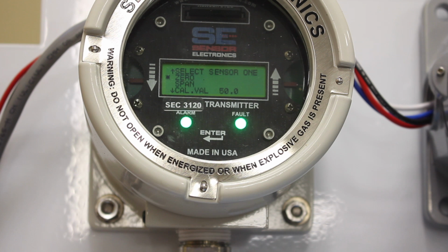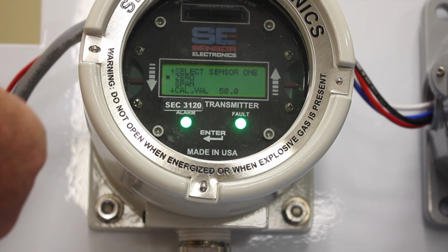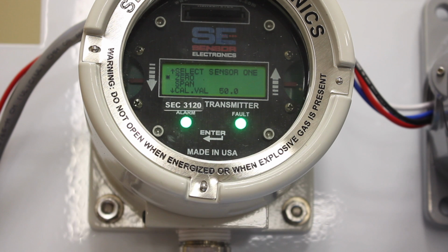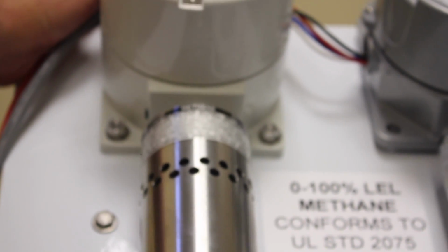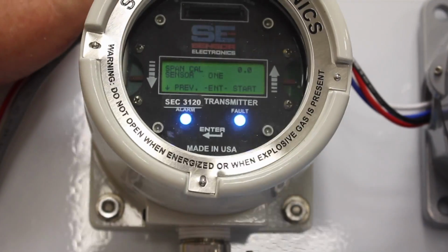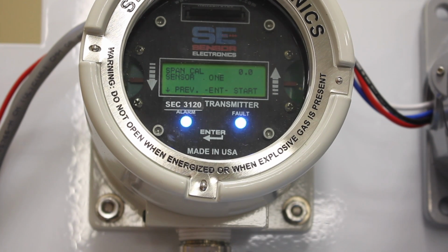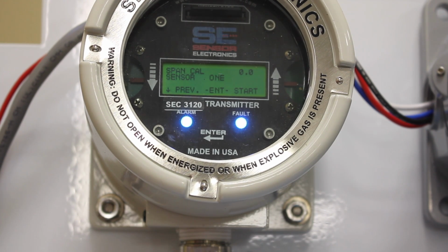And now we'll span the sensor. First of all, you want to check your cal gas value, and it's set for 50%, so that means you have to provide 50% LEL methane to the sensor to calibrate it, to span it. So we'll arrow down to span, we'll select enter, and then we'll connect our calibration gas cylinder and tubing up to the barb fitting on the bottom of the sensor.